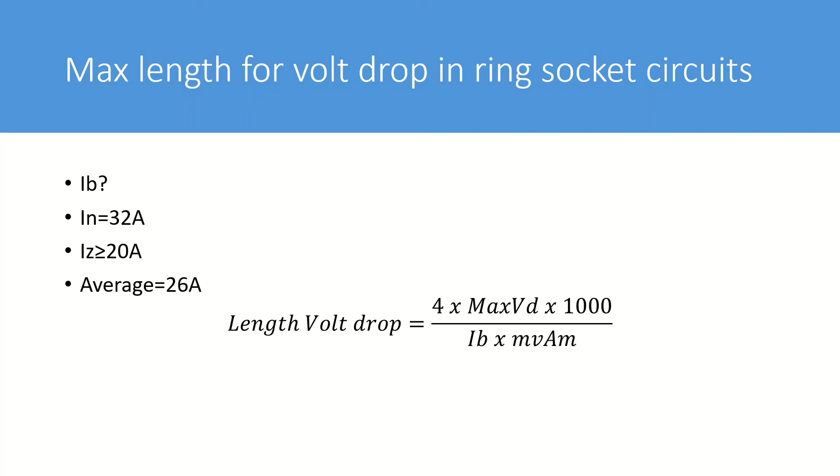Where a ring circuit is installed in accordance with appendix 15 of BS7671, a 2.5 mil cable can be protected by a 32 amp protective device provided that the current does not exceed 20 amps in each leg of the ring. However 20 amps isn't a design current.